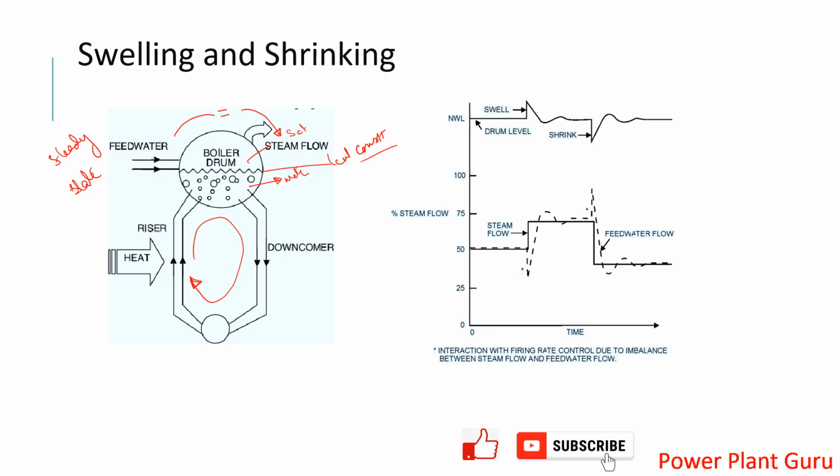Why the same? Because whatever steam you are taking, the same quantity of water you are feeding into the boiler, and your three element level control is taking care of that. But let us consider a case where this steady state process changes, and how it changes.